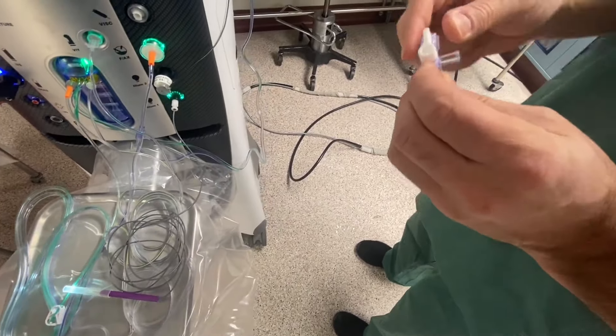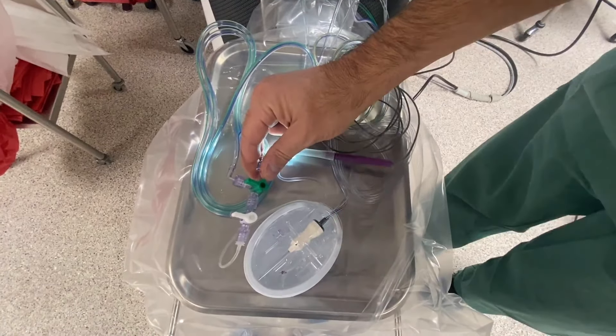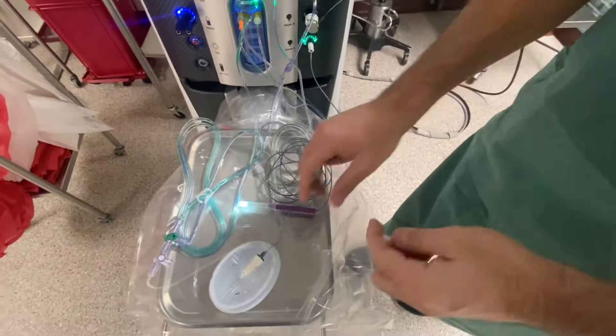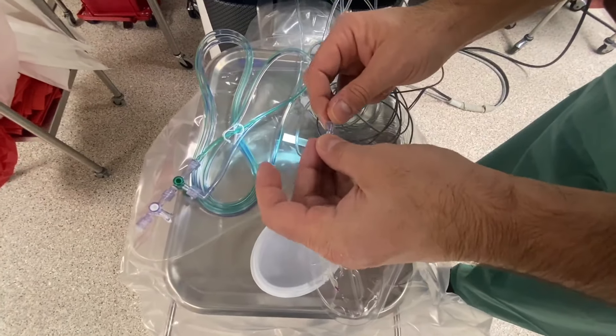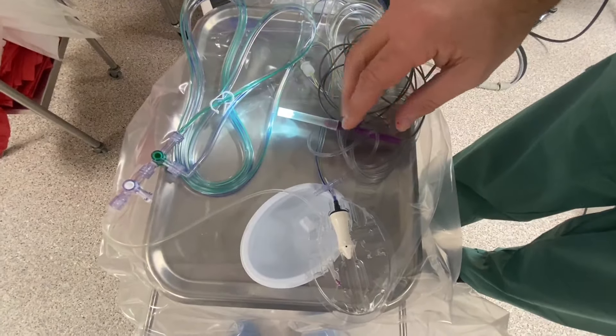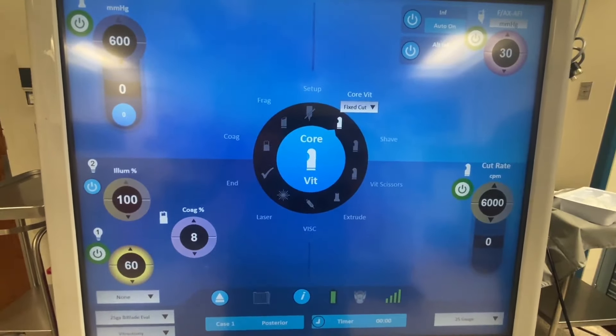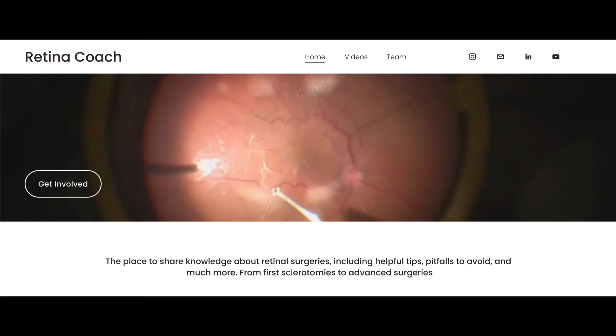In the accessory pack we also have an additional stopcock in case the surgeon wants to use it for gas injection during air-gas exchange. Two more items are a stopper for the cassette, which is used when the whole pack needs to be sent to the lab for diagnostics, and an adapter that goes to the extrusion line — this is where the soft tip cannula will go for the extrusion. These were the priming steps of the Stellaris Elite vitrectomy machine. Subscribe to our channel to avoid missing our new videos and share them with friends. Thank you for your attention!